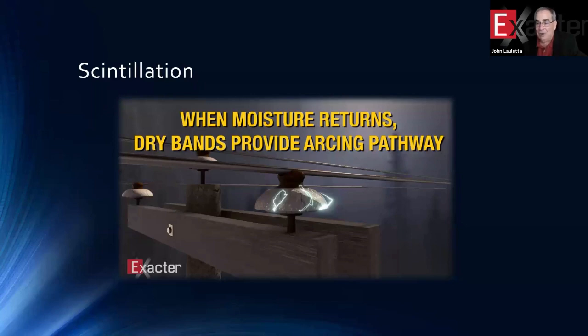Now, the good thing is when the dry bands form, they cause this process called scintillation. And scintillation simply means give off light. I've talked with utilities who will take two linemen in a car, and one will drive and one will hang his head out the window at night and look at the insulators as they drive down the road and look for that blue glow that comes from a very severely contaminated insulator for a changeout program. That's kind of resource laden and probably not a real safe way to do this work, but it's the same work being done. They're looking for an insulator that has these dry bands associated with it.